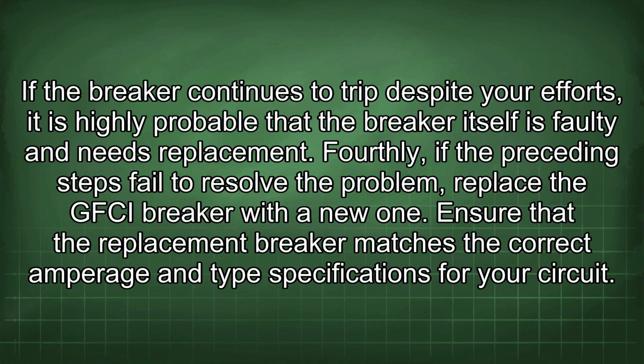If the breaker continues to trip despite your efforts, it is highly probable that the breaker itself is faulty and needs replacement. Fourthly, if the preceding steps fail to resolve the problem, replace the GFCI breaker with a new one. Ensure that the replacement breaker matches the correct amperage and type specifications for your circuit.